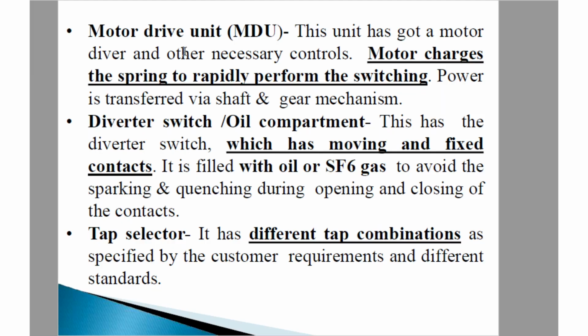Now what is the purpose of that MDU? It is a motor drive unit. This unit has got a motor driver and other necessary controls. Motor charges the spring to rapidly perform the switching. Power is transferred via shaft and gear mechanism.